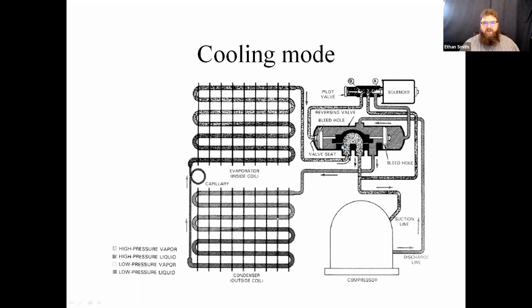So inside the reversing valve, we have this little thing we call a clamshell. We've got 3 pipes across the bottom, and that clamshell is built so that it will make a refrigerant passageway between 2 of those pipes at a time. Okay, we've got a pipe that comes into the top. The pipe that comes into the top is almost always the discharge line of the compressor. The pipe that comes out of the middle bottom is almost always the suction line for the compressor. You'll notice that there's some capillary tubes that come off of the top pipe. It's not pictured in this one. There's actually a capillary tube that comes off of here and goes up to this side of the pilot valve. Okay, we've got a capillary tube off the side of the reversing valve that comes up here, and another one that comes up here. Okay.